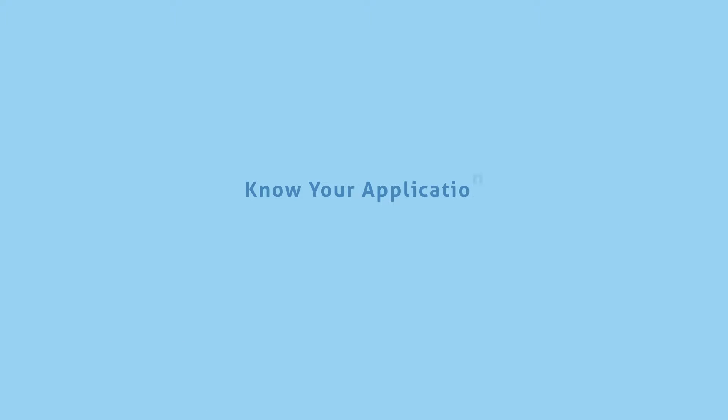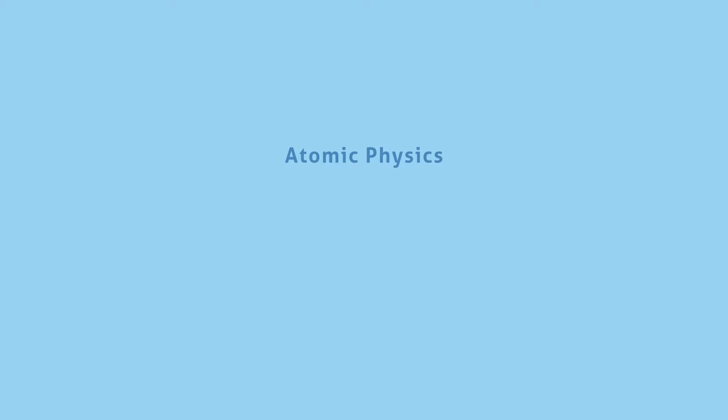Some applications require extremely deep vacuum. Atomic physics, field emission microscopy, and x-ray photoelectron spectroscopy may require vacuum pressures between 10 to the minus 3 to 10 to the minus 9 millibars. For these applications, a diffusion pump, ion pump, or turbo molecular pump may be the best or only choice.